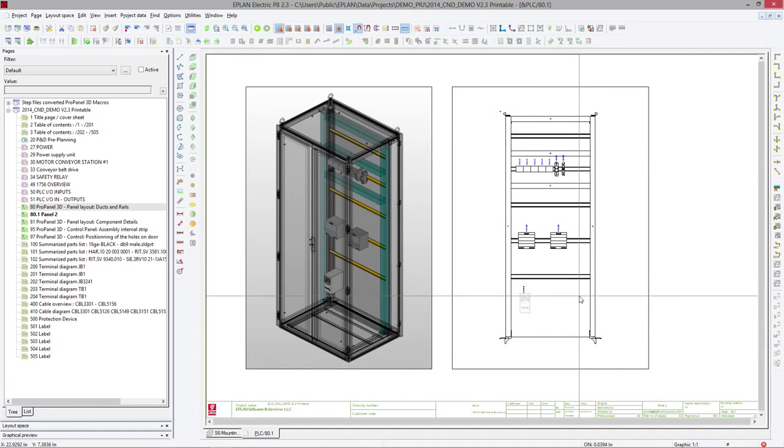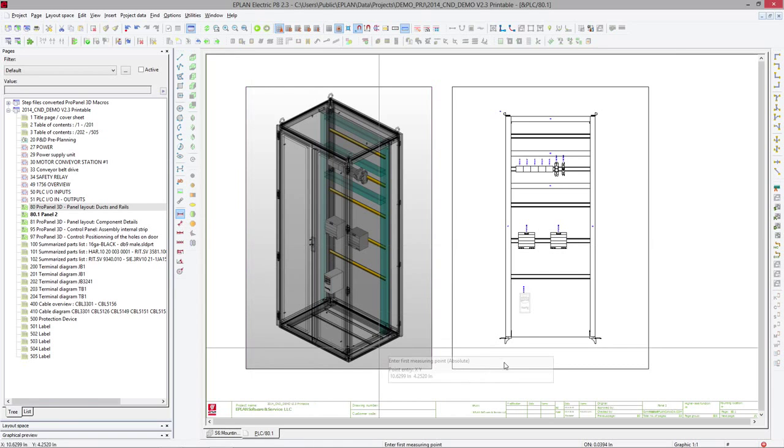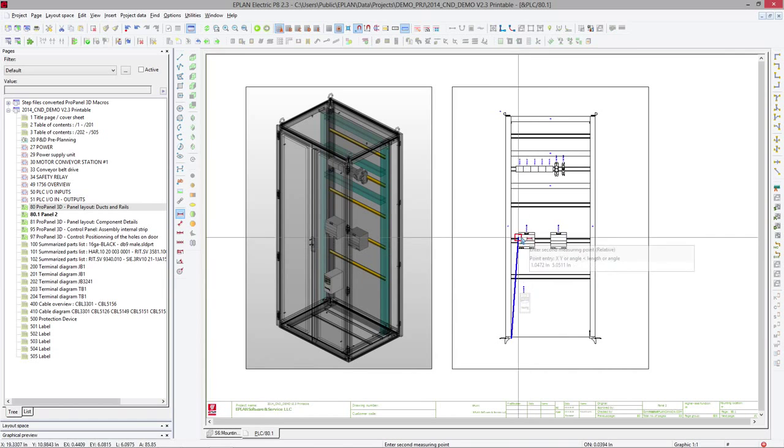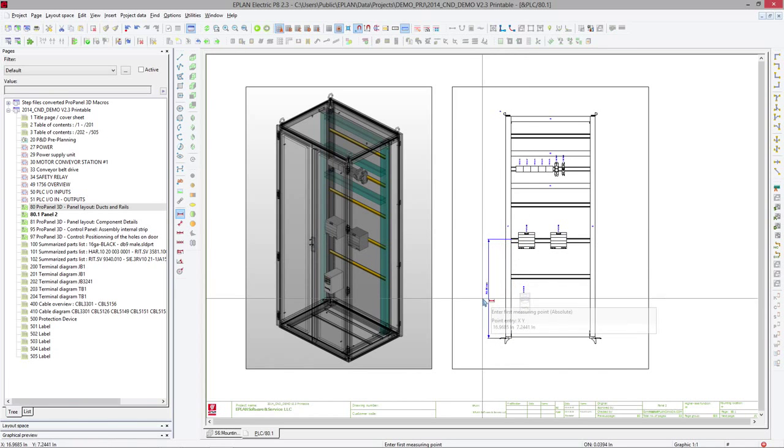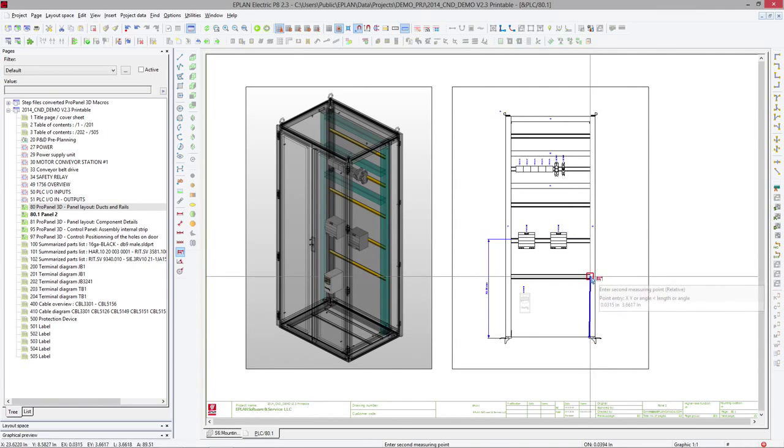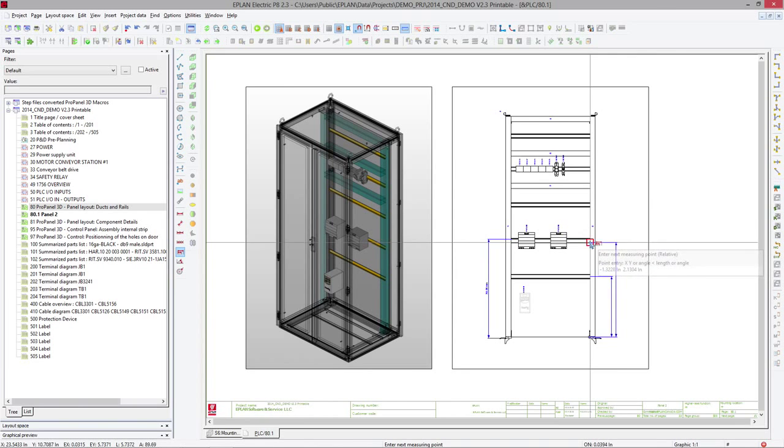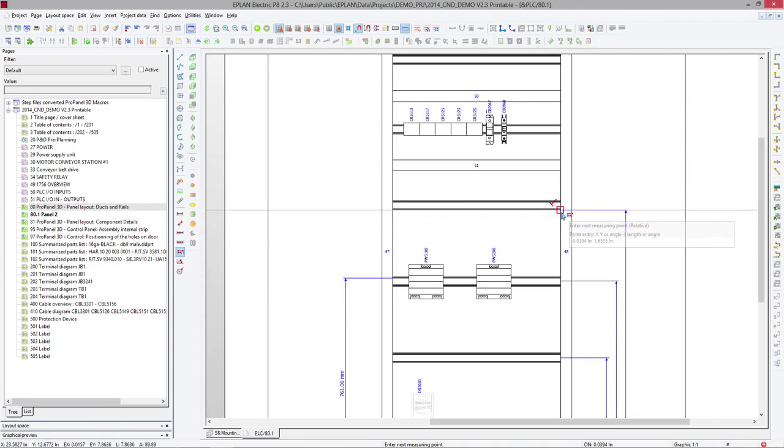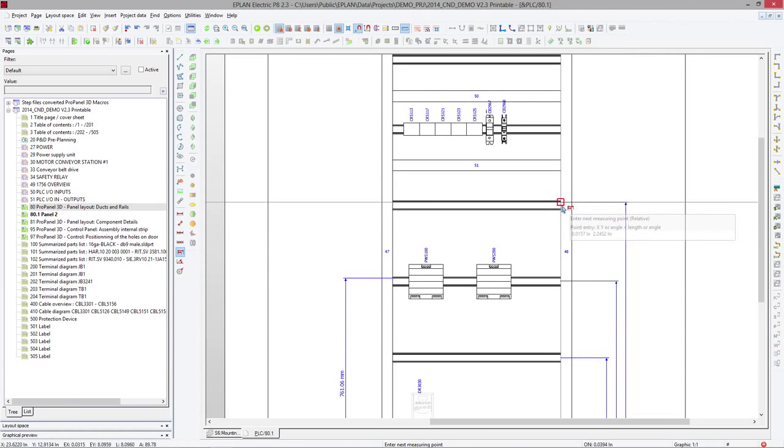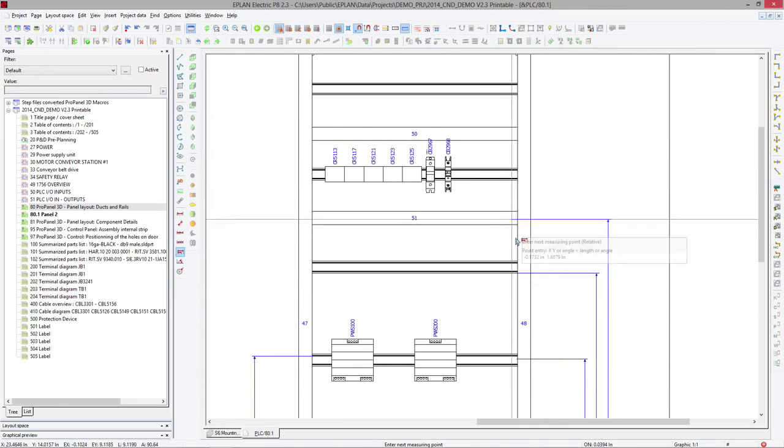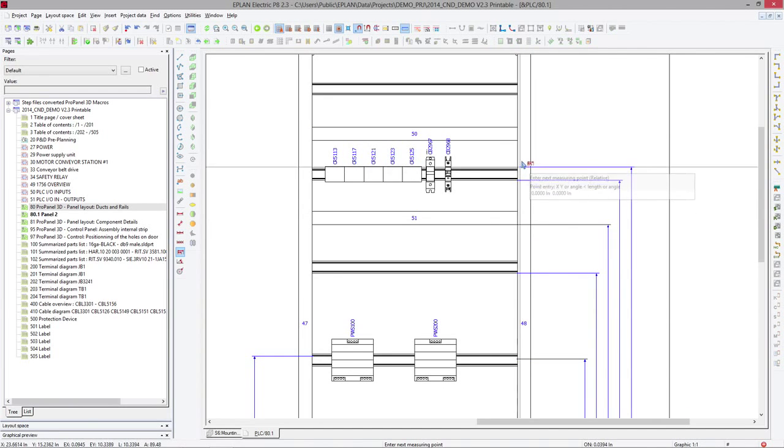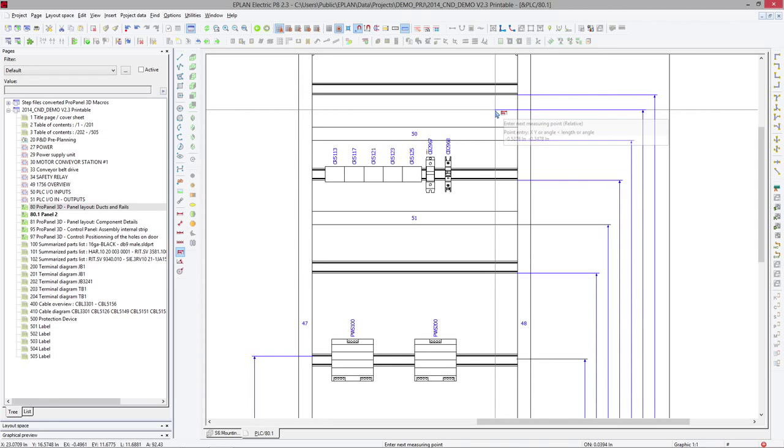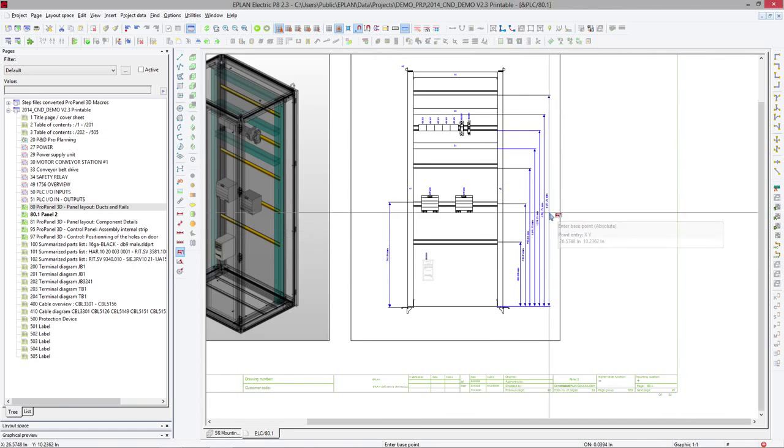And this is the time when you add some dimensions. So these dimensions could all start from the same spot and say, okay, I want to give him this dimension. Or you can actually do it a little bit more fancy by creating a baseline. So this is the first dimension you want. This is the second dimension. Let's just zoom in here. That's the third dimension I want. So you could, of course, if you choose to just pick the bottom of the DIN rail, the bottom of the objects, it's up to you what dimension you're giving the electrician. And when you're finished, there you go, you have all the dimensions.